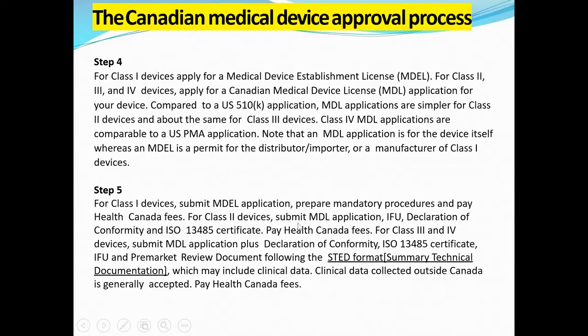For class 2, submit the MDL application and the IFU, the instructions for use. The label is very important, and the intended purpose has to be mentioned. Then the declaration of conformity and the ISO 13485 certificate, and pay Health Canada fees. For class 3 and 4 devices, submit the MDL application plus the declaration of conformity, ISO certificate, IFU and a pre-market review document following the STED format, that is the summary of technical documentation, which may include clinical data. Clinical data collected outside Canada is generally accepted. Then pay Health Canada fees and go ahead.